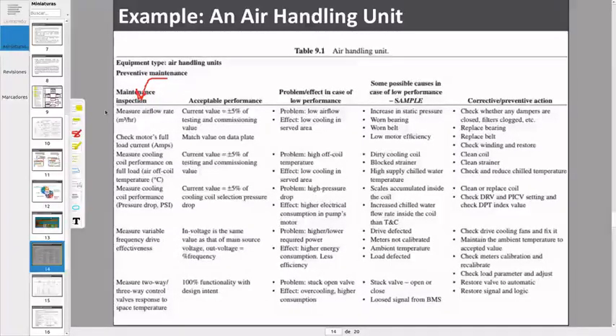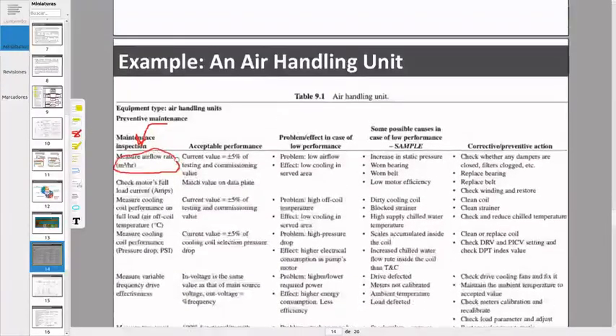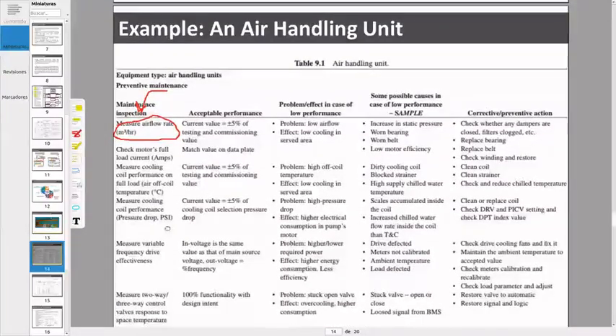We're just measuring. So we measure the air flow rate of the machine. We said if it's within 5% of the testing and commissioning values, then that's acceptable, and you don't need to do any special maintenance. However, if it's beyond that value and you have some problems happening, let's say low air flow rate, there will be some reasons for it.